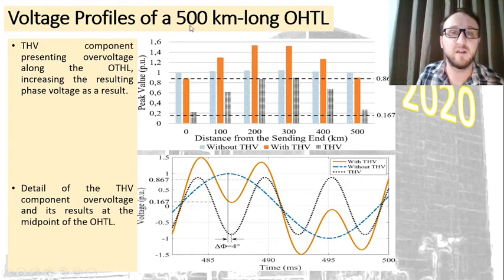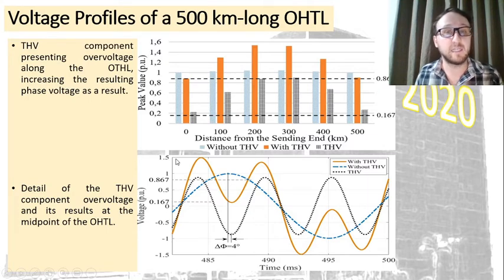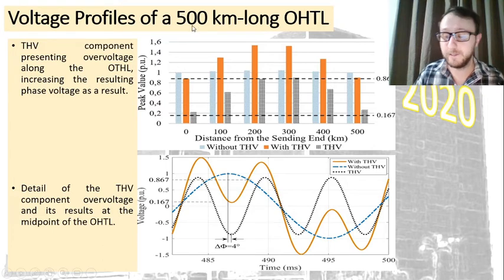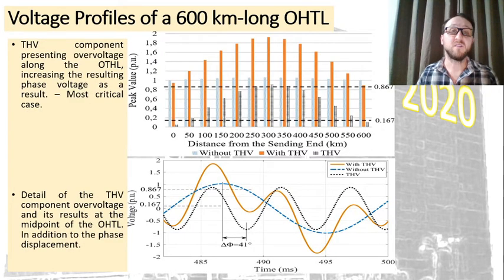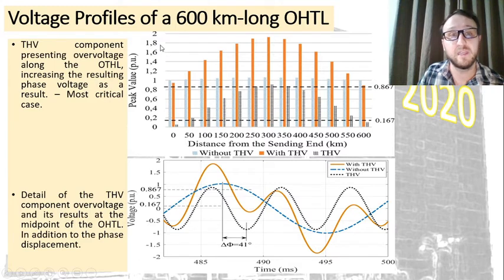For the 500 kilometer line, we have already surpassed this value, it reaches 1.5. So our THV technique is not appropriate for this long line. And finally, for 600 kilometers, this is the profile, and we see at the midpoint it goes up to 1.8 pu, and here we have the time domain waveform.